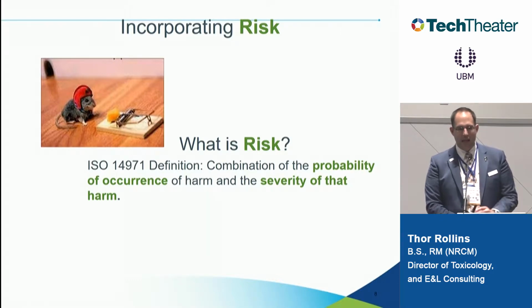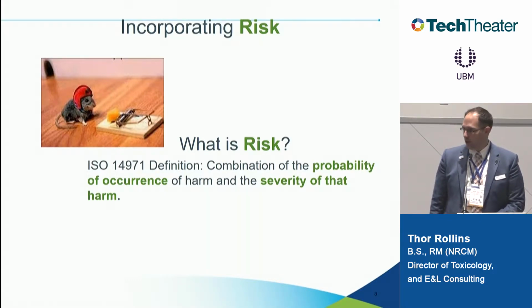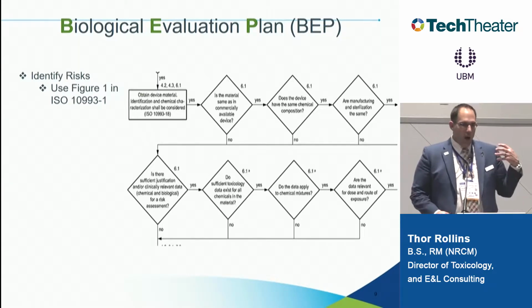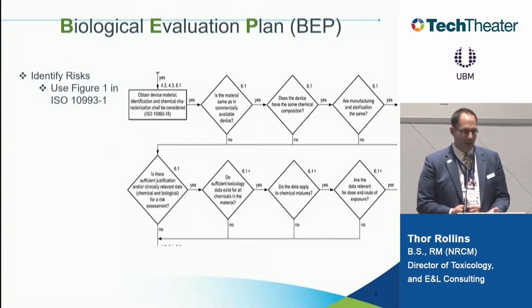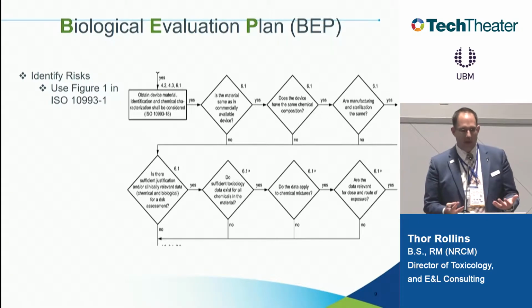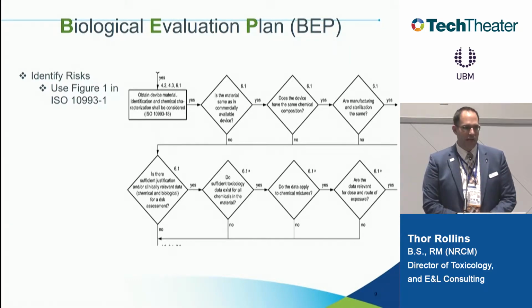And the new ISO 10993-1 actually relies heavily on the standard. So it is something we should have in our toolbox. But I also want to talk about with this risk-based approach, it's not new. It may be new to a lot of customers who've been checkboxing biocompatibility for the last 4, 5, 10 years, but the approach isn't new in the standard. So this current flow chart has been in this ISO 10993-1 standard for a while. And it really is your initial risk-based approach.